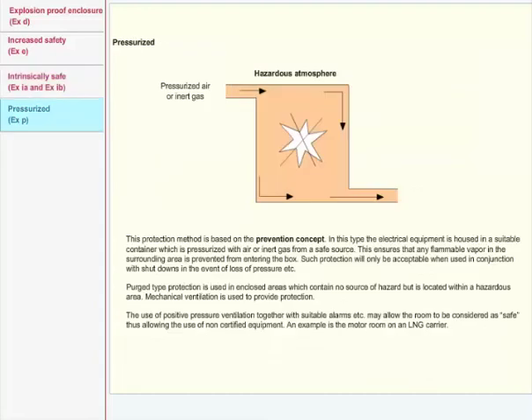Pressurized. This protection method is based on the prevention concept. In this type, the electrical equipment is housed in a suitable container, which is pressurized with air or inert gas from a safe source. This ensures that any flammable vapor in the surrounding area is prevented from entering the box. Such protection will only be acceptable when used in conjunction with shutdowns in the event of loss of pressure, etc.